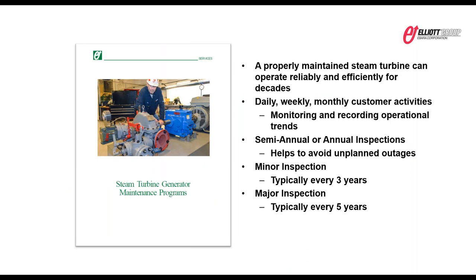The daily and the weekly and the monthly activities, the monitoring of the equipment, recording trends and things like that, that's usually the customer's or the operator's responsibility. We may come in on a semi-annual or an annual basis to look at certain things. When we come in for an annual inspection, that may or may not be when the unit's running. If it's running, we're not going to open the casing or anything like that. We're not going to cause you to shut it down just so we can look at it. We're going to do visual inspections. We're going to check all the seals, and we're going to check for leaks of oil or steam or even water.